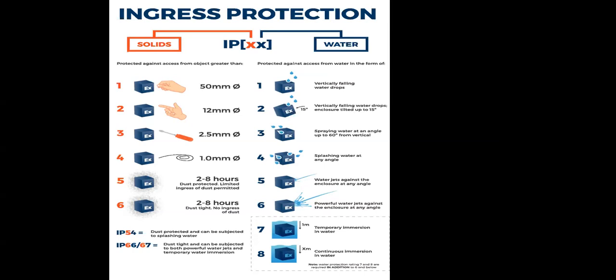Here is another important thing I want to mention. For example, I have selected a panel of IP54. In IP54, what type of dust am I protecting against? Dust protected, limited ingress of dust permitted, 2 to 8 hours, and 4 means splashing water at any angle. There are a lot of panel manufacturers who will offer you IP54, and we ask how we can ensure it is IP54 protected. They will offer a proper laboratory certificate, like CPRI or National Test, from a competent laboratory. You will find that the certificate shows a full panel with equipment installed inside.